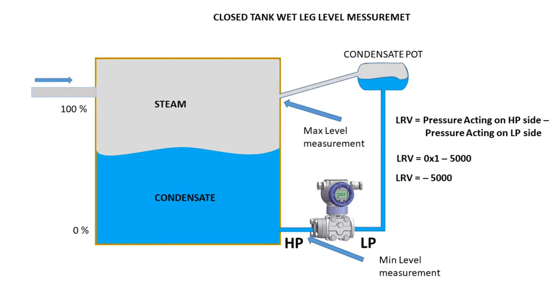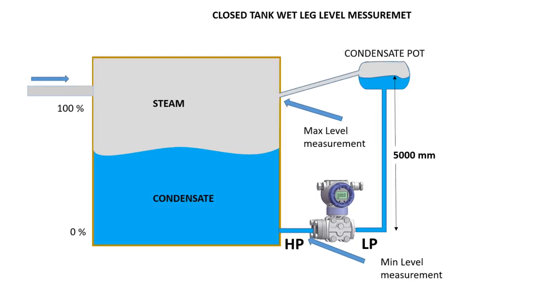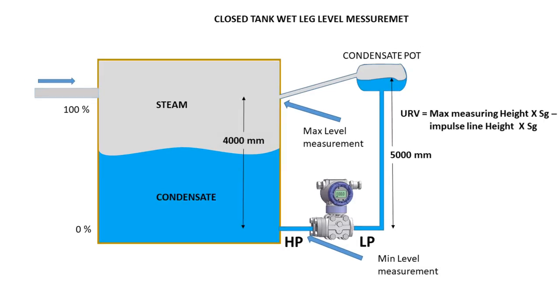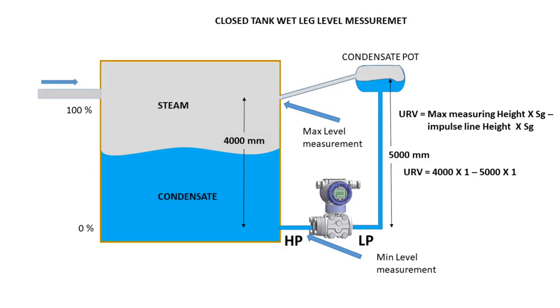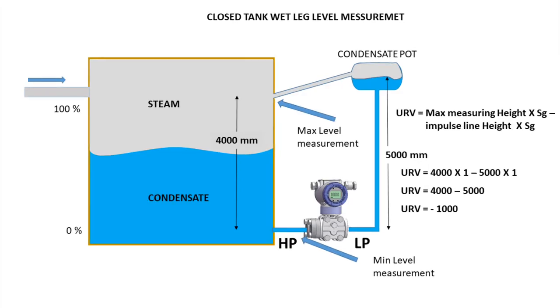So the LRV equals minus 5000. Next we calculate URV. For URV, use the equation: maximum measuring height times specific gravity of liquid, minus impulse line height times specific gravity of filled liquid. The maximum measuring height is 4000 millimeters. So the URV equals 4000 times 1 minus 5000 times 1, which gives 4000 minus 5000, so the URV equals minus 1000.